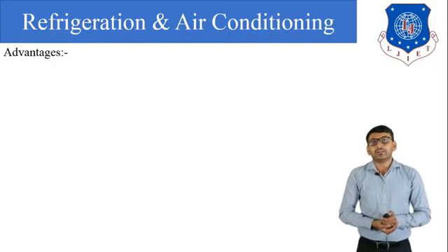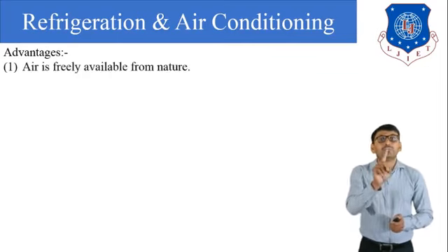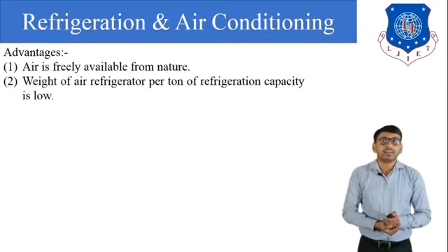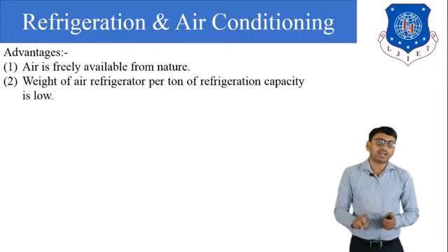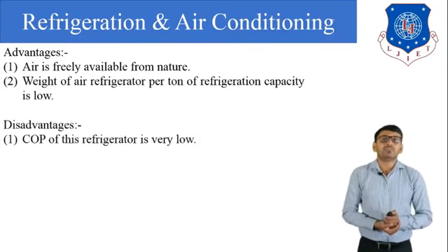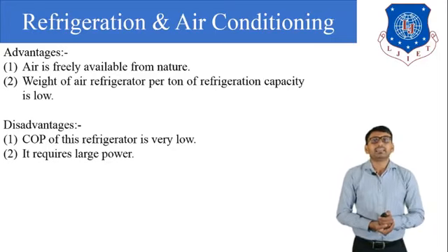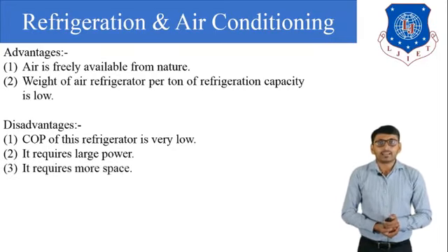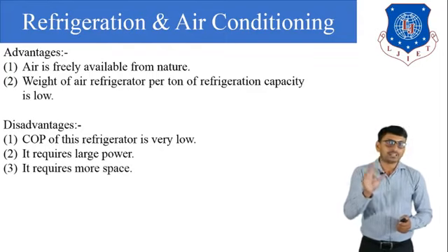Now there are some advantages of the air refrigerator. First, air is freely available from nature. Second, the weight of the air refrigerator per ton of refrigeration capacity is low. So there are two advantages of the air refrigerator, and some disadvantages also. First, the COP of this refrigerator is very low. Second, it requires large power. Third, it requires more space. So this is about the air refrigerator.